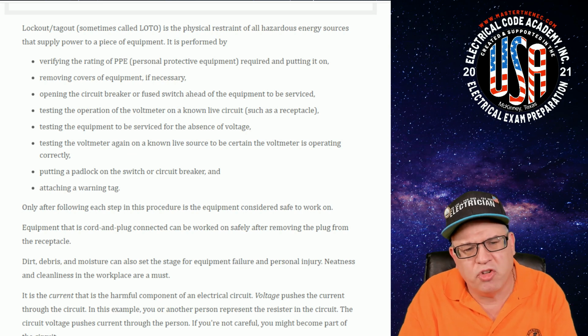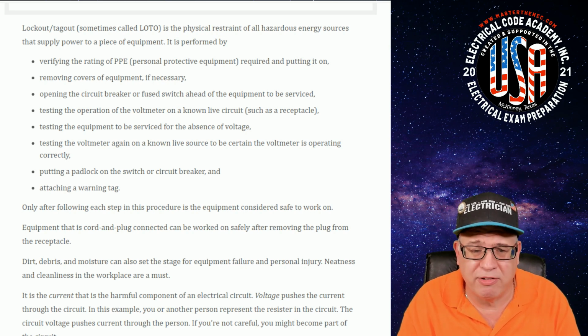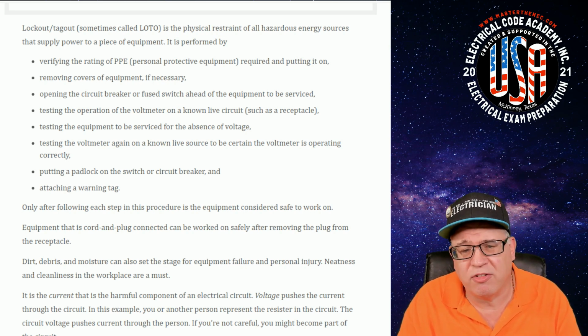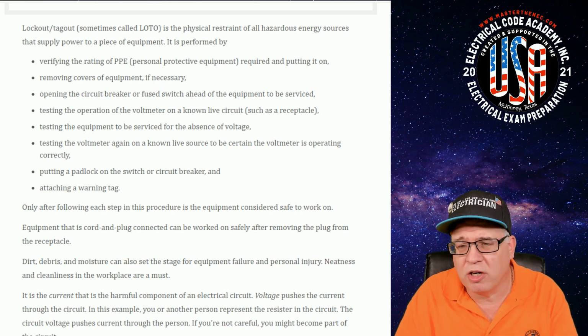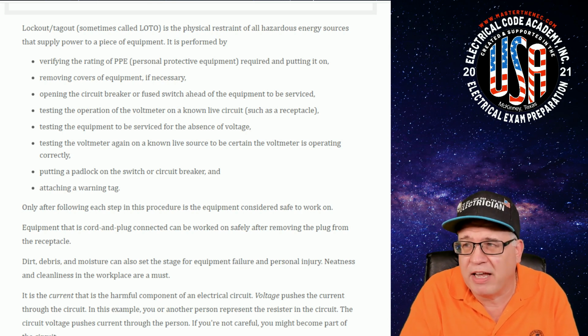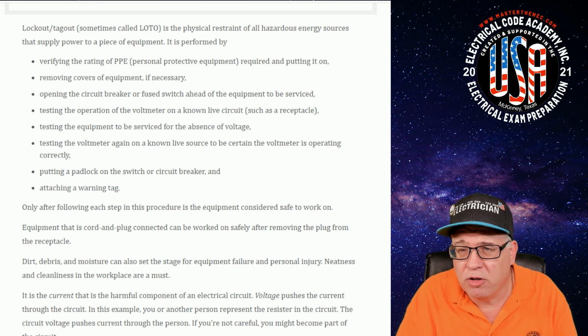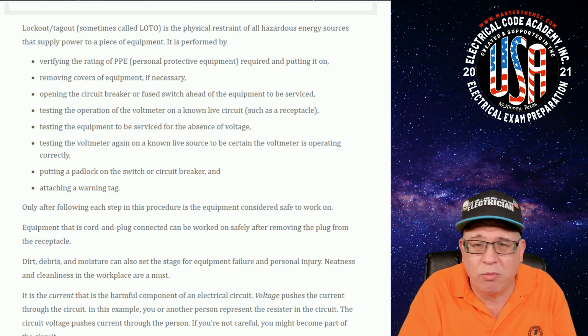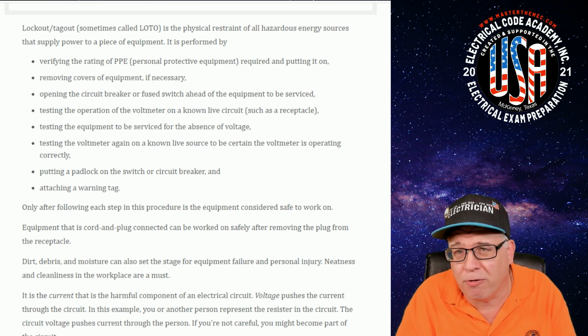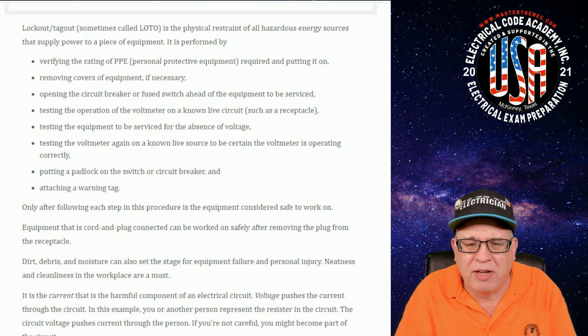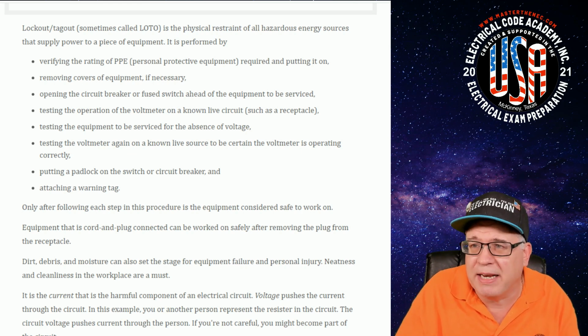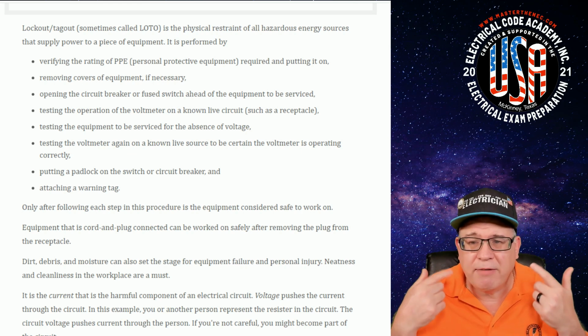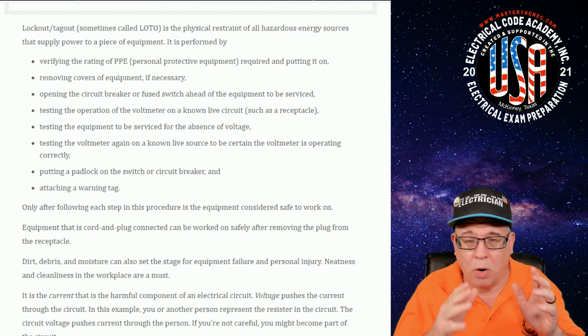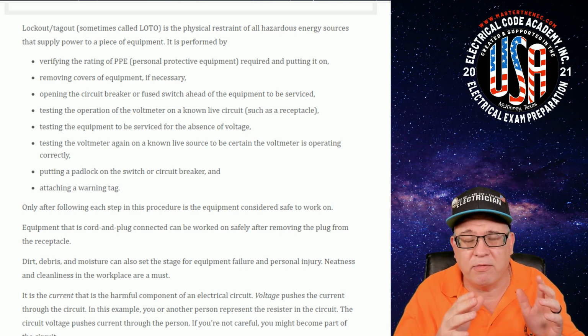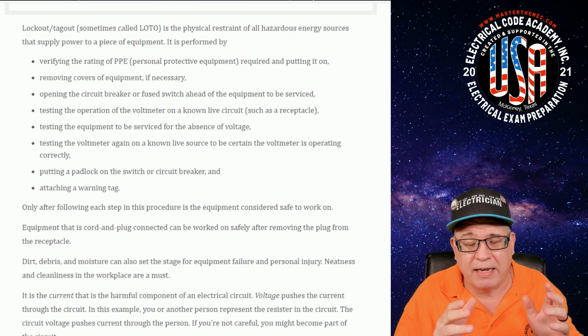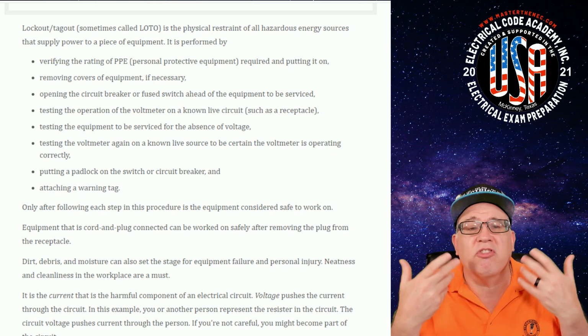Now, dirt, debris, and moisture can also set the stage for equipment failure. Using equipment placed in locations that aren't rated for that environment, like using a NEMA 1 in a location where you really needed a NEMA 3R for rain and moisture. All those types of things. When you're going to go into that equipment, you should start having red flags come up. When you see something, you go, whoa, wait a minute, this isn't rated for this environment, and I'm getting ready to go into this thing. Your caution level should start to rise.